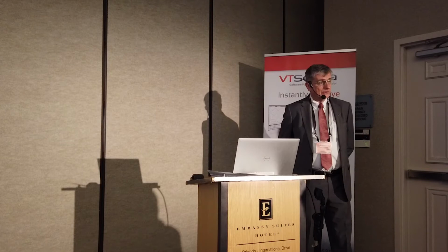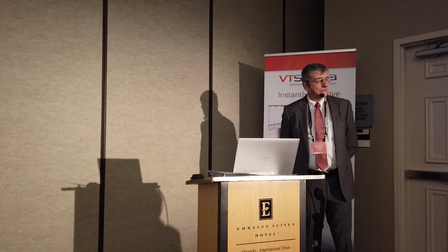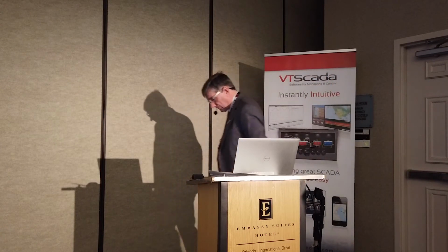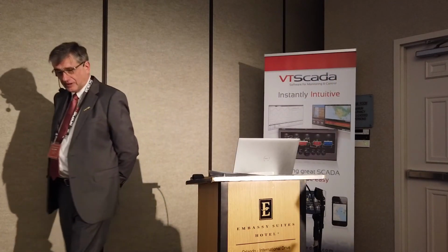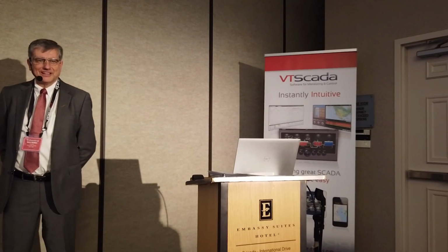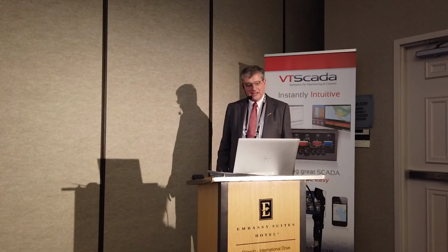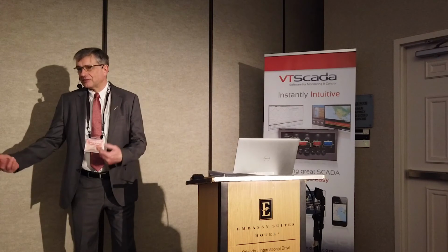The fact that an alarm occurs too many times, that's not exactly production information. That's more of a configuration information for those involved with managing or configuring the system. If I've got an alarm like I saw at Sacramento a year ago, this alarm on average is going off every 5 minutes. You kind of ask, doesn't somebody get annoyed by that? They just ignore it. It's noise. Well, you really should be doing something about that. But just getting your alarm systems more meaningful so that people don't get numb to hearing about things that are irrelevant.